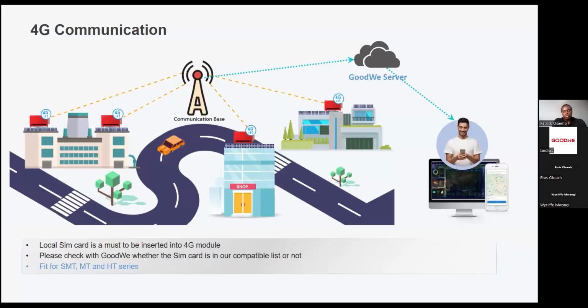And if you're doing isolated installations, then the inverters can connect through 4G dongles, each inverter connecting to the same server, the same plant. You can consolidate all these isolated plants to make a single, centralized plant. And this minimizes cable costs, installation time, and many other difficulties that come with linking all these by wired connection. So through 4G connection, we can do installations using our inverters.